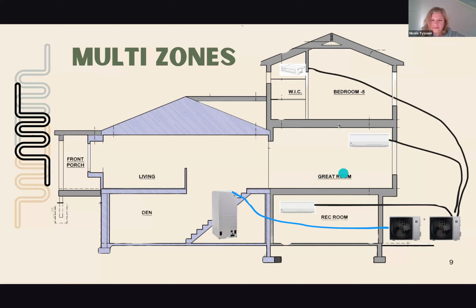Then on the third floor, we used the ducted mini split because we have a bedroom, a bathroom, a closet, and an office, and a small attic space. You can see where the unit is, which makes those units very easy to install. We were able to duct that and provide enough heat and cooling for that whole upstairs.